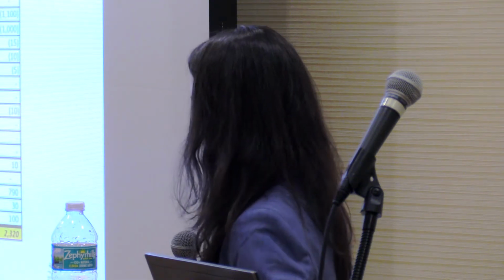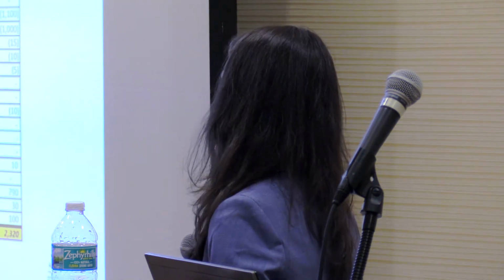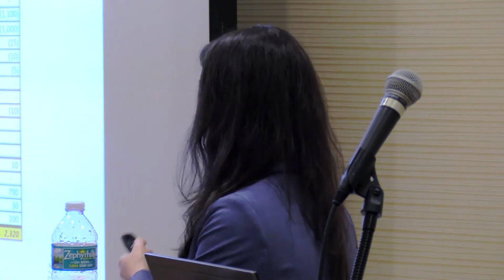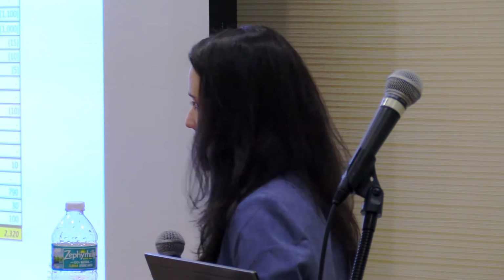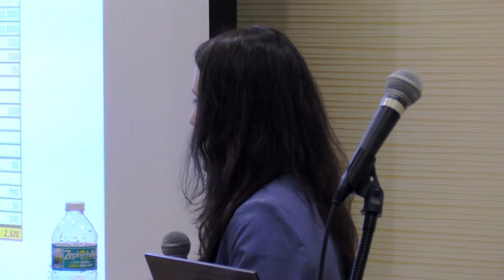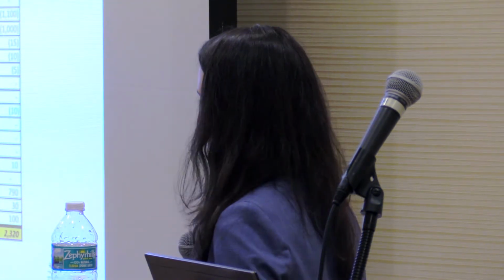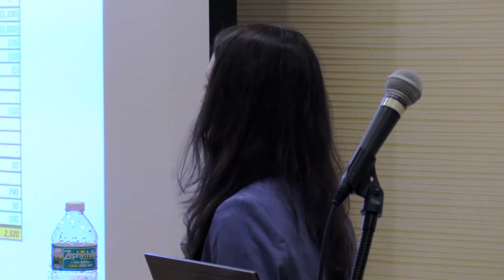We also did have the balancer go through and check K-factors on the VAV boxes, had him take some readings at the cross-flow sensors to make sure that the air was distributed correctly once you got downstream of the air handling unit. And again, the answer there was no. I mean, like Ryan said, you start with 15 VAVs and you cap a duct and then you come back, and who knows if you adjusted for the new stuff in the system, right? So this was a really useful exercise, not just sitting down with the balancer and taking the raw data, but also just doing some basic math. Am I getting out what I'm putting in?